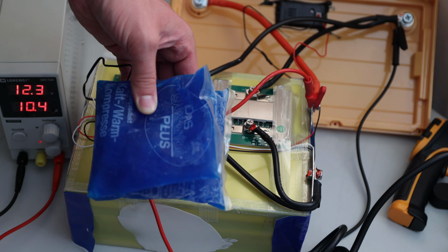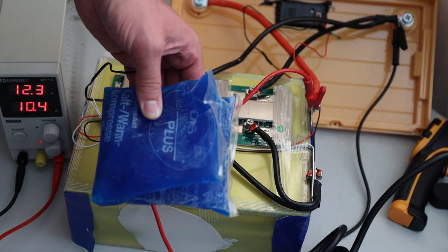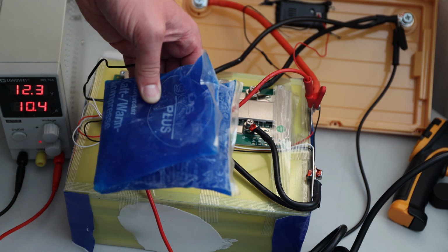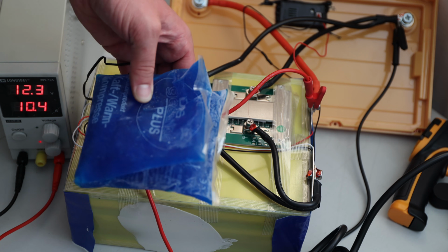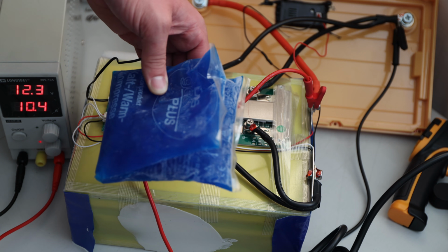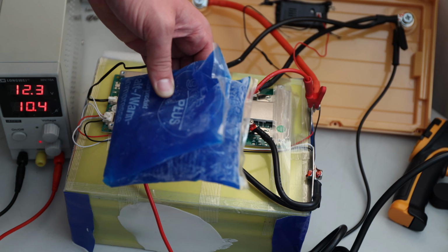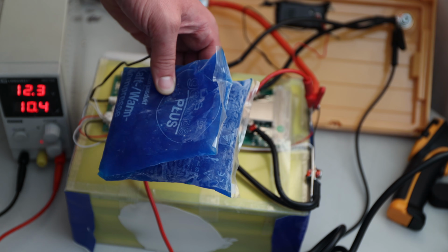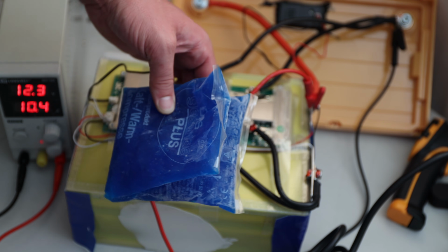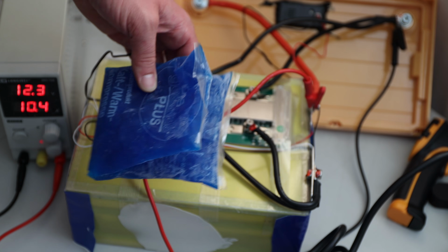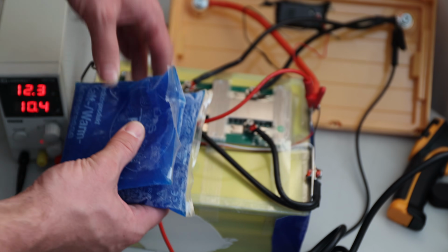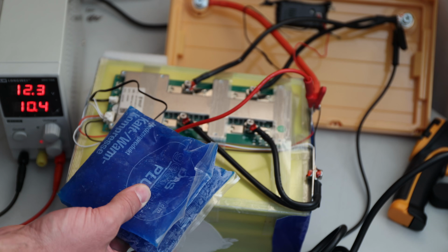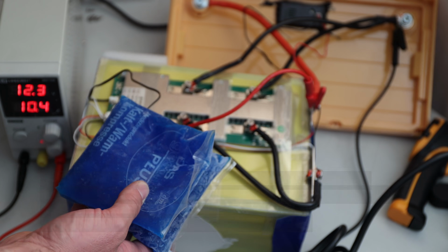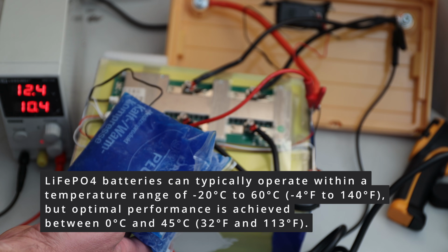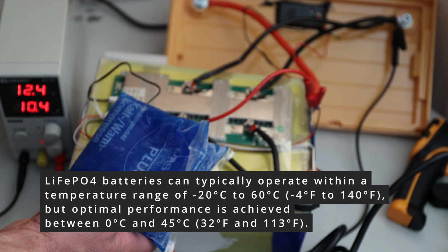Remember, when you're charging lithium iron phosphate below 0 degrees, this is when you damage the cells. You can discharge, this cell is rated up to minus 10 degree operating temperature, it says. Discharging below freezing temperature, around 0 Celsius, is not a problem until it gets way too cold. That's depending, I think I read between minus 10 and minus 20 is the temperature limit for this chemistry.